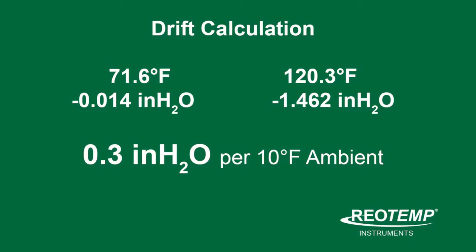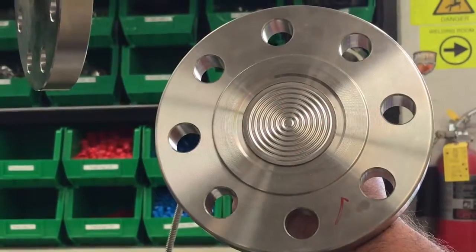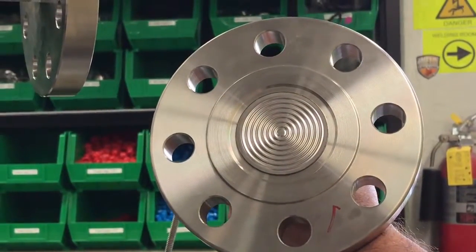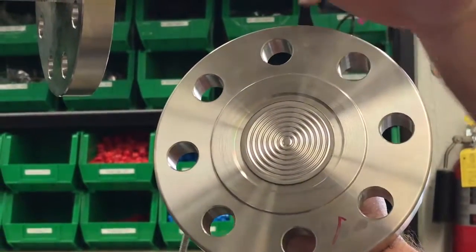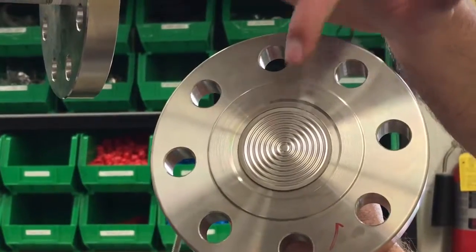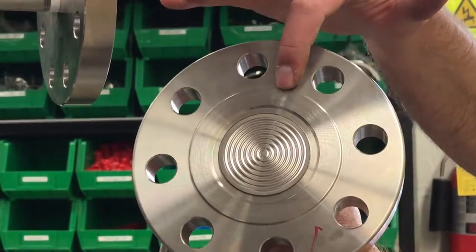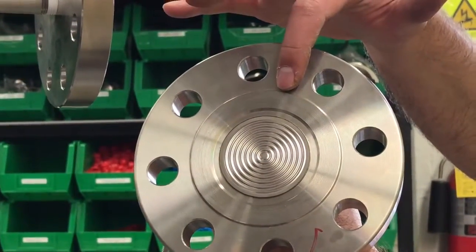The best way to combat this drift is to increase diaphragm size, which not only adds sensitivity to the assembly, but also helps eliminate pressure drift due to temperature fluctuation. Unfortunately, a flush face seal only allows you a limited area to fit both the diaphragm and the raised face gasket surface.